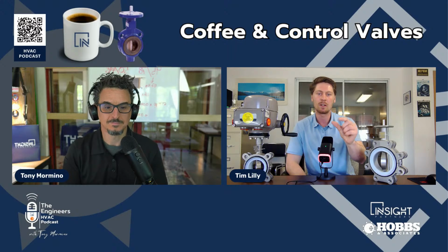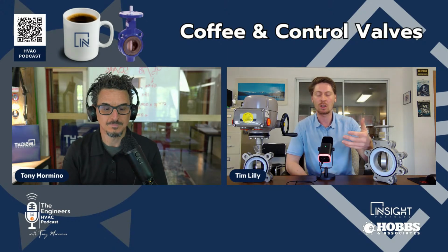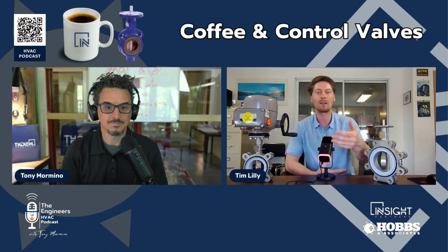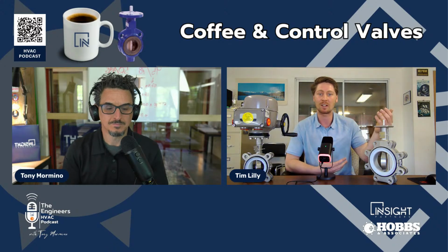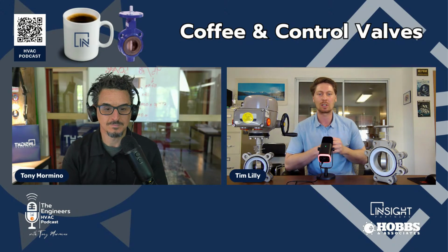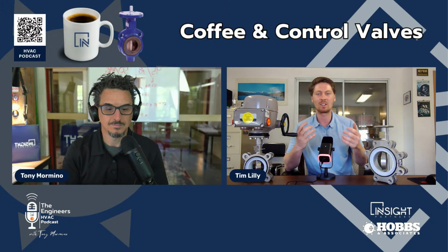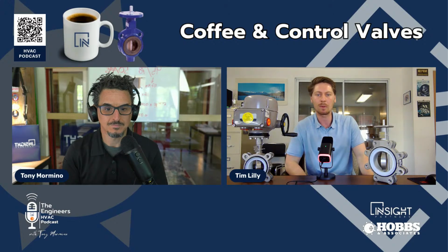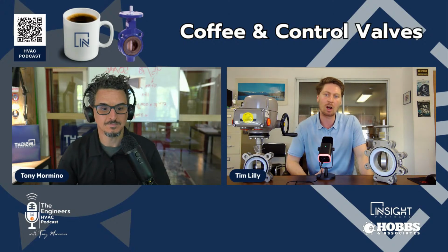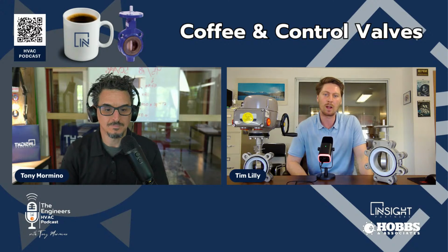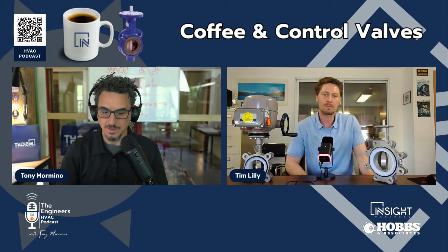If you go to a globe valve, your opening's a little bit smaller. So a lot of times if you have a 6-inch pipe, you might have to bump up to say an 8-inch or a 10-inch valve, and that reduces some of your cavitation and concerns going through the pipe. So it's really an art to size a control valve. Yeah, you got to know what you're doing.